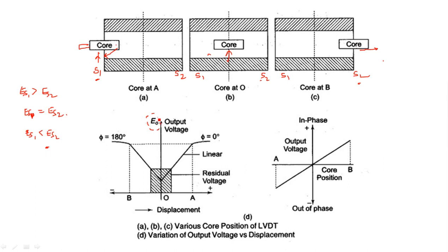Now we take the output voltage at center point O. When the core is at position O (center), equal EMF has been developed in both cases. Moving toward point A or point B changes the output. Even at zero, some residual error exists practically. The phase of A is out of phase with B — one is at zero degrees and the other is at 180 degrees.